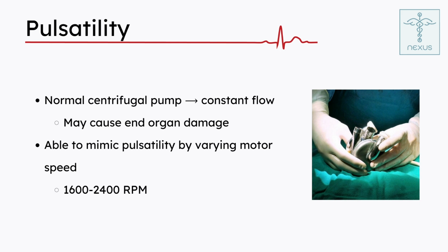In theory that might also damage some of the end organs, for example the kidneys, the liver, maybe even the brain. So the way they got around that is they're able to mimic pulsatility by varying the speed at which the motor is running. They vary it between 1600 and 2400 RPM, and that gives a level of pulsatility, so you can actually feel someone's pulse even if they've got this motor running inside them.